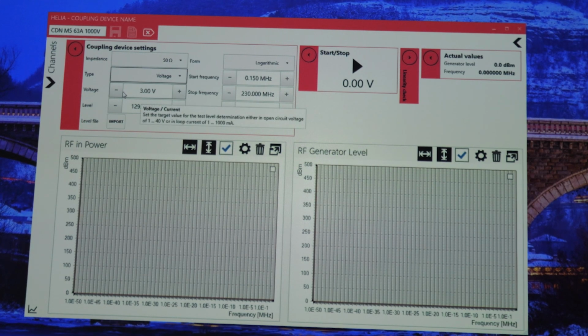For the test level at the device under test, when you change this, it'll change the dB microvolt test level, but for today's example, we're just going to try to calibrate a 1 volt drive level, so let's stick that to 1 volt. You could adjust the frequency and the step size. I'm going to speed this up today, so I'm going to change the step size to 8% per step increase to speed it up.